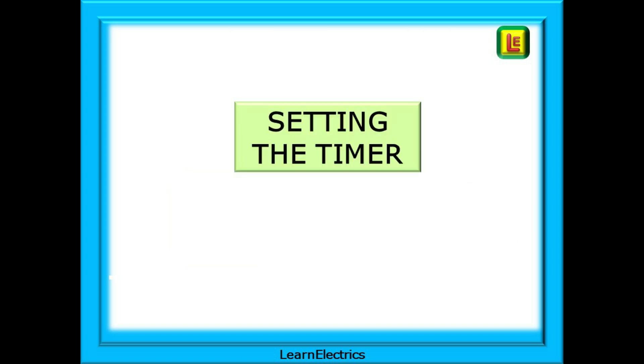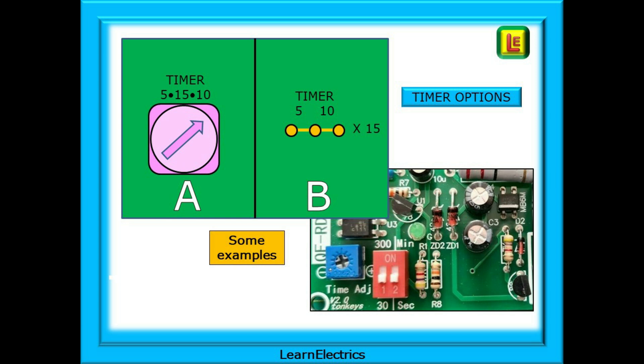How do we go about setting the timer? Every fan manufacturer will have a slightly different method of achieving the timer settings. Generally the overrun times will be something like 5, 10, and 15 minutes, or some other sequence of time. Some timers will also allow a zero time setting so that the fan exactly matches the light — light on, fan on, light off, fan off. These settings can be a simple three-position switch, three pins in a shorting link, or a digital switch setting.